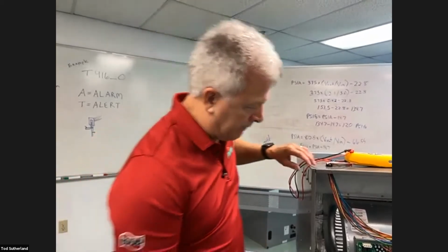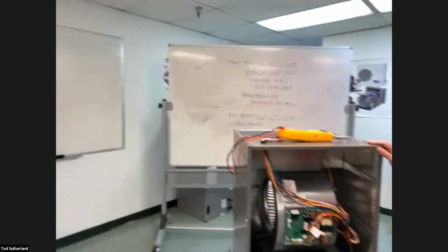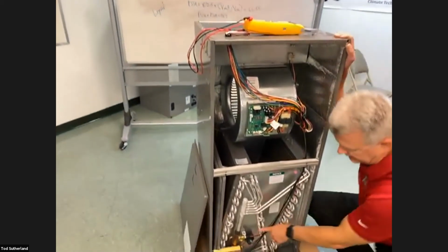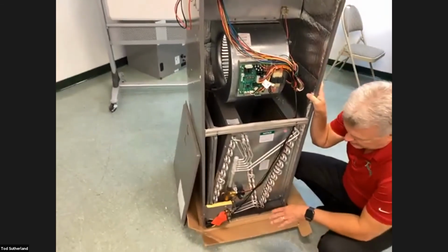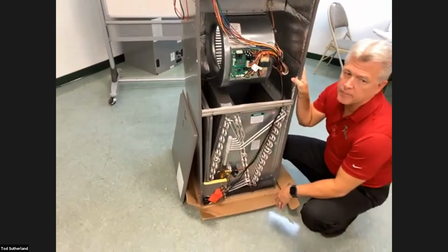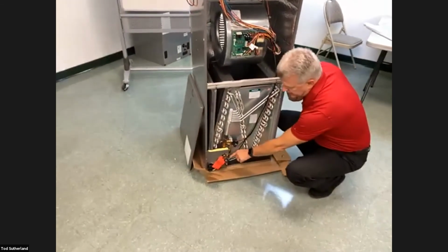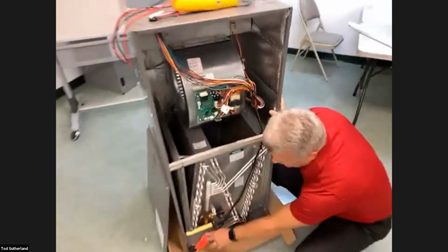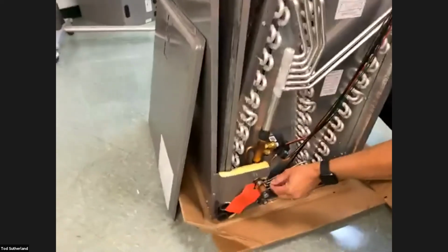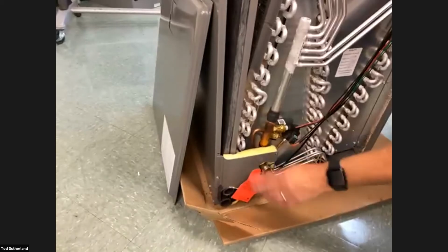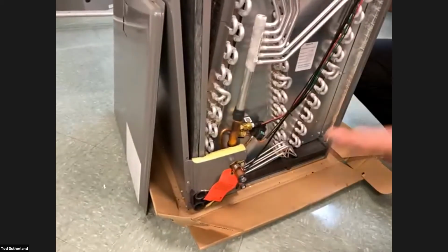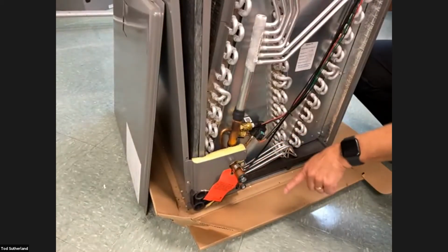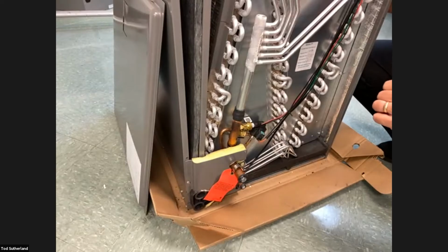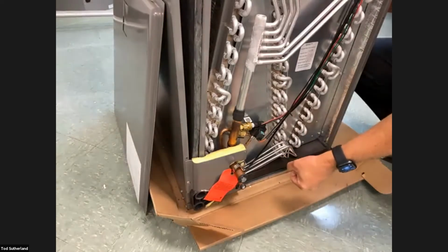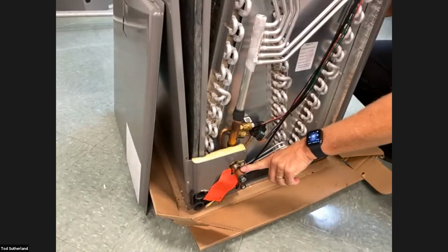Now, same thing here. If you look at this, we're going to come down to here. This is the same stuff that we were talking about a little bit earlier. We have a thermistor here for the expansion valve. This is just loosely zip tied here. You're going to cut that zip tie, pull this out of here, braze your lines in, and then attach this. The air handler comes with some insulation to wrap that thermistor on the pipe once you're done. Again, this is a 10K ohm thermistor.